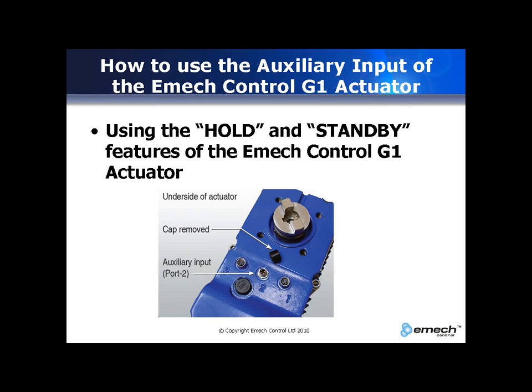This video will show you how to configure the Emech G1 actuator to enable the hold and standby features. The auxiliary input port of the Emech actuator allows the actuator to accept a binary signal from a device such as a flow switch, a flow sensor, a level switch, or from a manual switch, or it can accept a signal from a PLC device. This binary signal is then used to enable the hold and standby features.